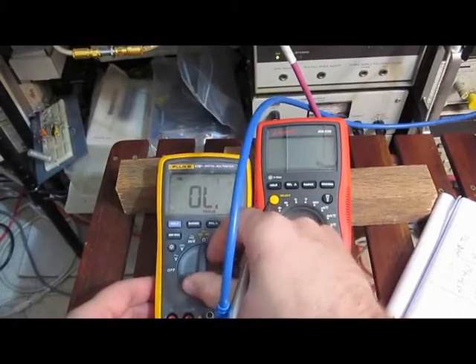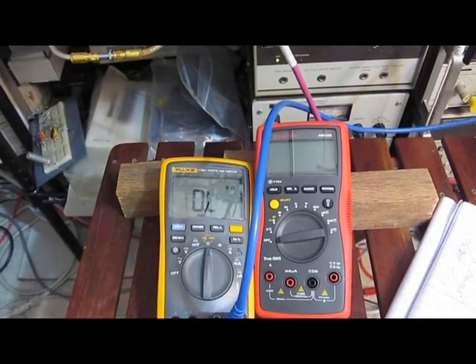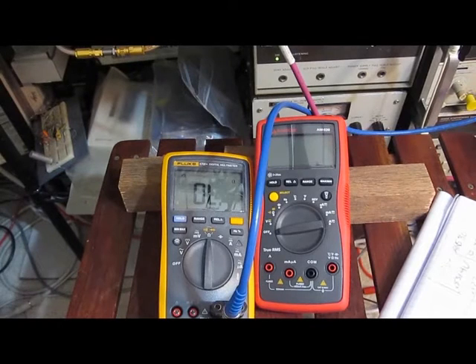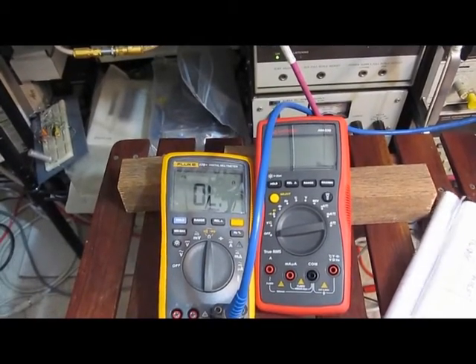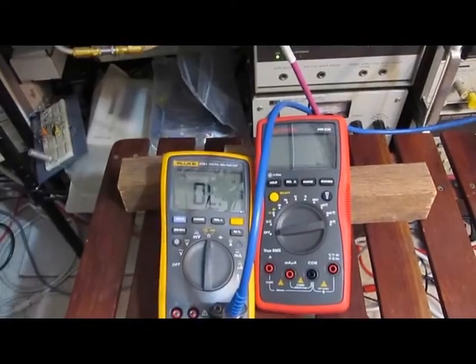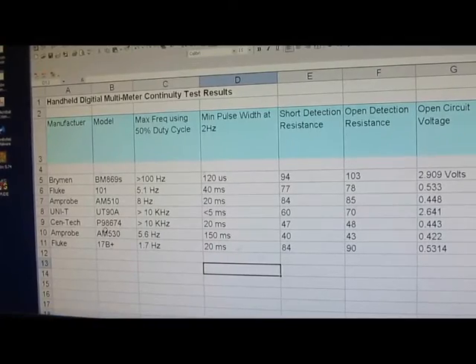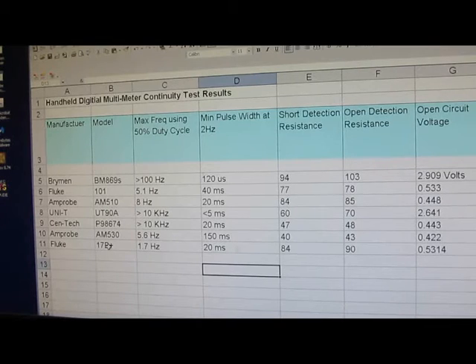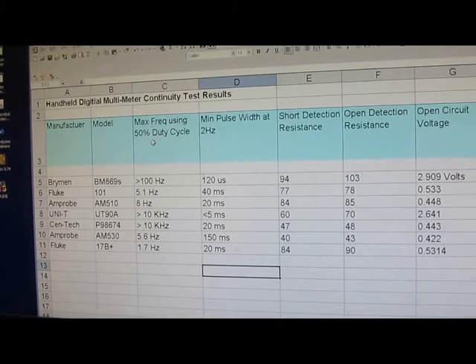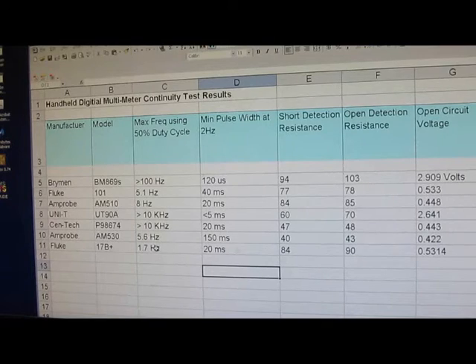And we'll do the same thing with the Fluke. Looks like about right here. Maybe one wider. So this is the data I've collected so far. Down here we can see the 17B plus. With a 50% duty cycle wave going into it, it was good to about 1.7 Hertz. Compare that with 5.6 for the Amprobe, 8 Hertz for the other Amprobe, the 510.